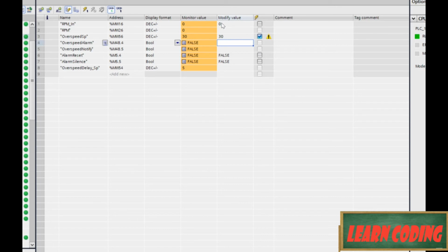I don't think we had any other conditions. So if I put this up to something like 26,000 input signal, that should give us an alarm within 5 seconds. So now we're at 188 RPMs, 5 seconds, tick tock, and I don't see any alarms. So we should be overspeeding.